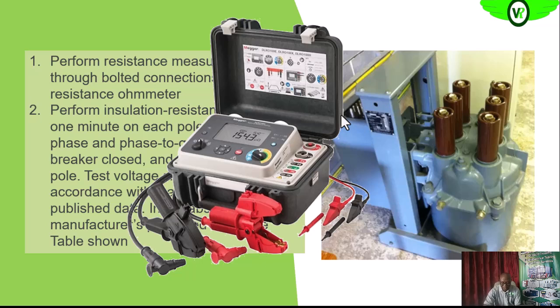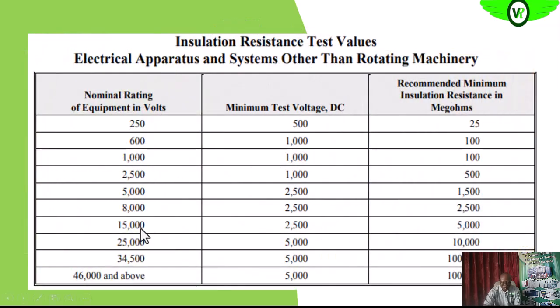So this is an example of this is a micro-ohm meter that we can use to do our insulation, our resistance tests. Okay, so this is the table. So since we are looking at medium and high voltage, so these are the voltage region that we'll be looking at. Okay, from 1000 volts and above to about 34,000. That is from 1000 volts, because we are looking at medium and high voltages. So these are the test voltages, and this is the minimum insulation resistance we should expect to have when we carry out the insulation resistance test. So we can use this table as a guide to know when our insulation is failing.